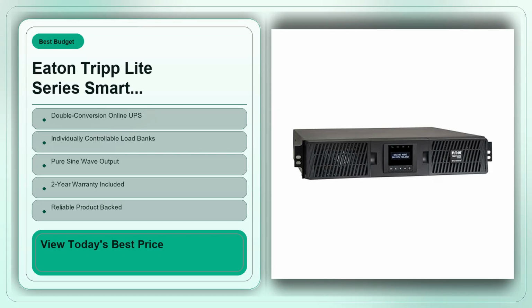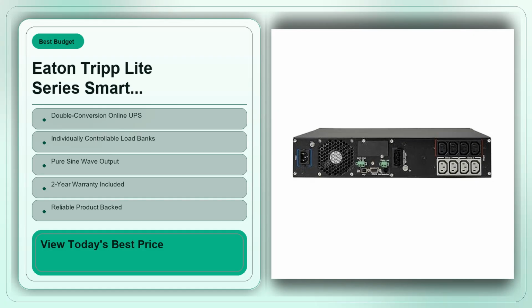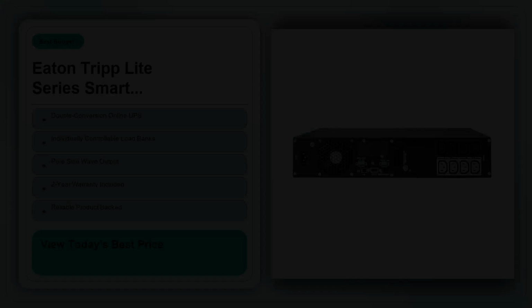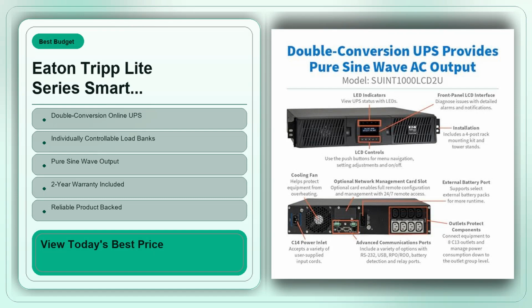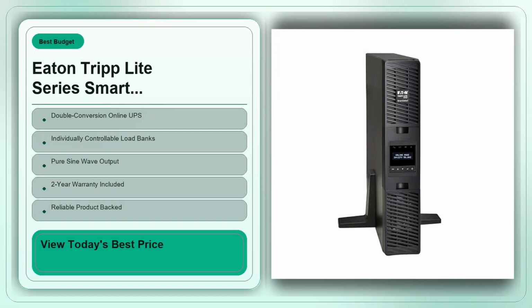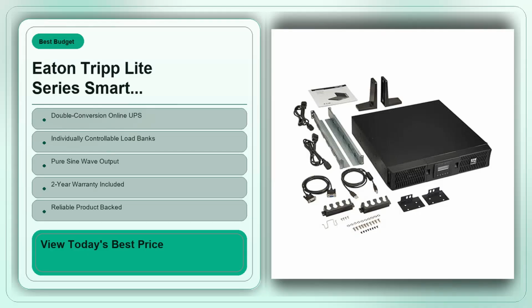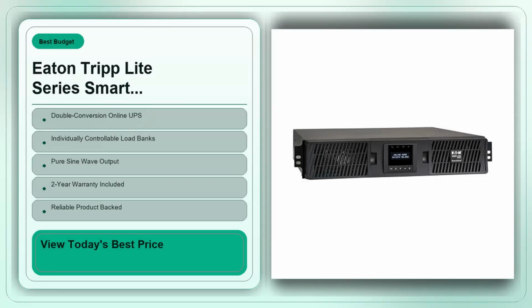Battery runtime is another reality check. The manufacturer's spec sheet will tell you up to 10 minutes at half load, but in practice, you'll see those numbers shrink if you have any high-power devices plugged in. The UPS is designed more for bridge power, keeping you online long enough to initiate a proper shutdown rather than for extended outage coverage. If you need to keep a small server running for an hour during a storm, you'll want a larger capacity unit, or an auxiliary generator.